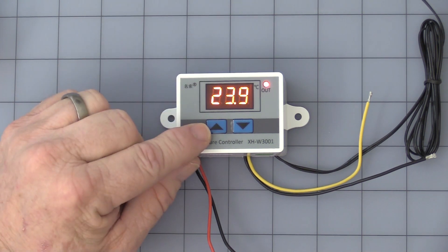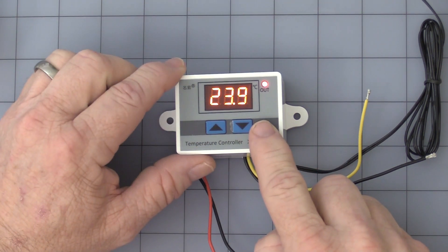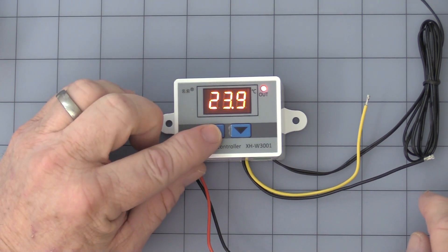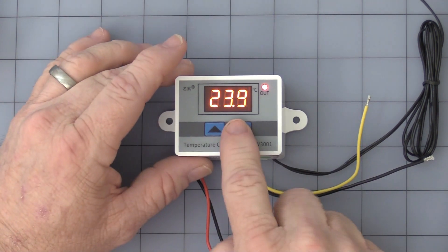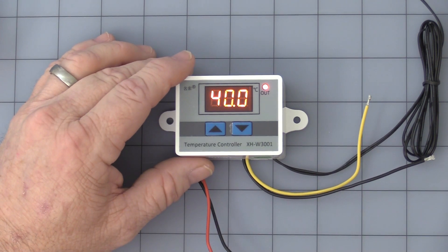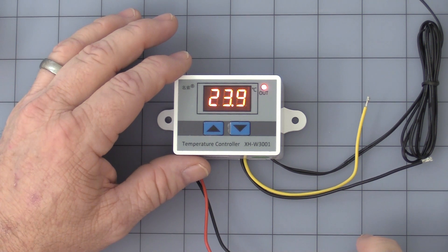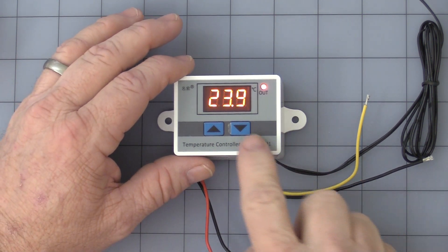When this one is lower than this setting, that's what's called heating mode. And what that basically means right now is that I would have to get this up to 40 degrees Celsius for this relay to turn off. It's a good time to learn how to reprogram the setting set points for the temperature.